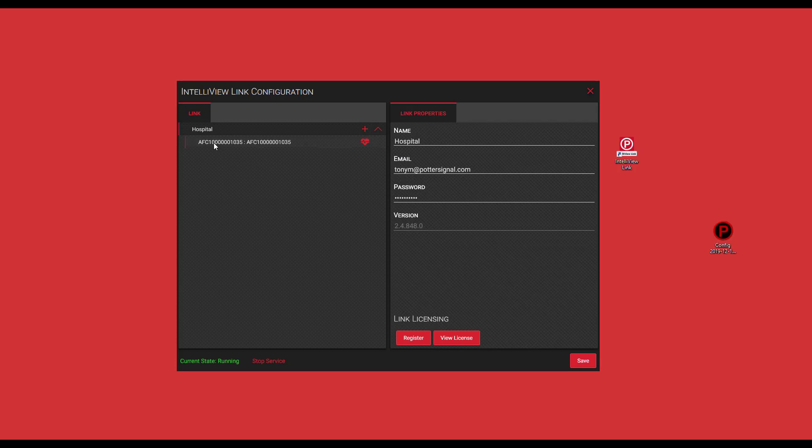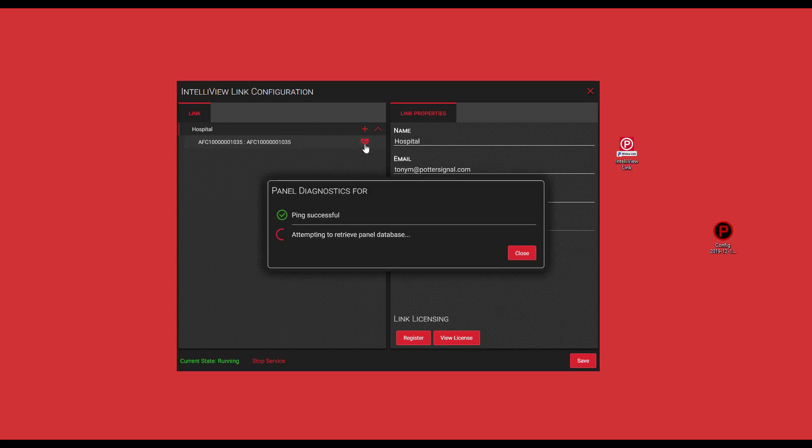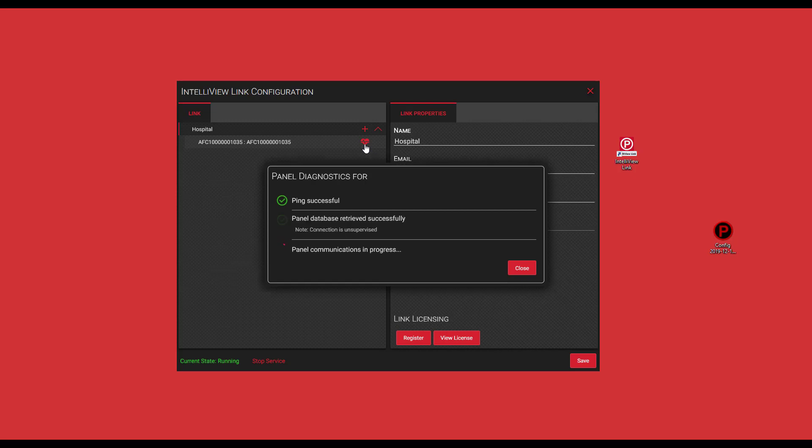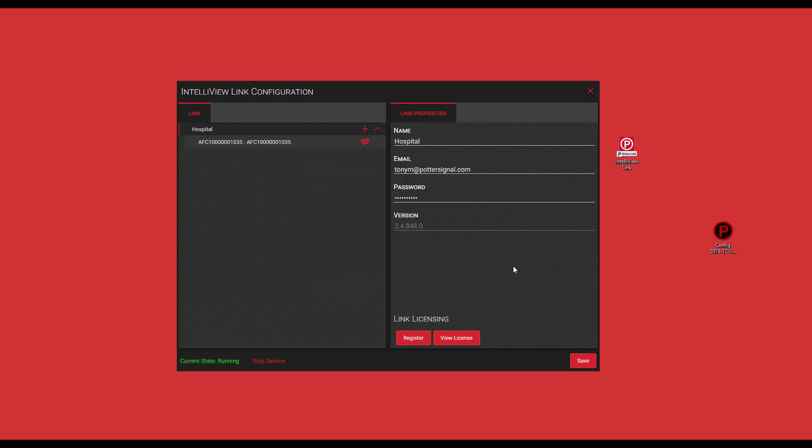Now you're going to see your panel located here along with the little heartbeat symbol which runs panel diagnostics. The nice thing is once you do that, it's going to go out and ping the control panel to make sure it's communicating correctly. It's also going to try and retrieve that panel database. If you ever have trouble communicating to one of your control panels, this will be one of the first steps that we would suggest you use. Now we'll click close.